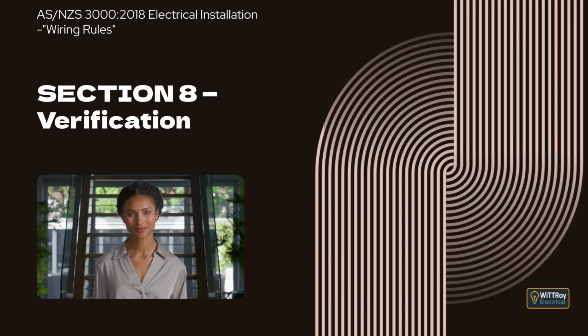These are circuits where fault protection is provided by automatic disconnection of supply, where the circuit supplies one or more socket outlets, and where those socket outlets are not protected by an RCD with a rated residual current of 30 mA or less. The notes explain that the testing method verifies that the protective device will disconnect an earth fault current within the required time and touch voltage limits.